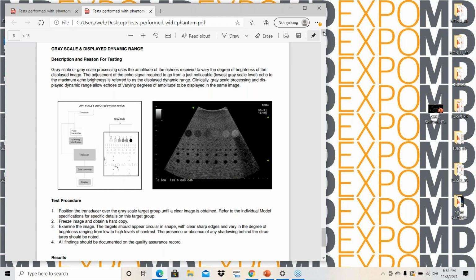I normally make it a mid one, so I have no problem reaching it. If I'm at 18 megahertz, I'm going to have a hard time getting here. So I try to get something around the 10 megahertz, depending on what the customer has. So I'm clearly getting beyond, and then it doesn't matter if you can see them all. It's the system's ability to differentiate, not the frequency. And so I only need to do this test on 1, and I will definitely have a printout, because an image quality problem, a lot of times, is based on this. The system loses its ability to see a specific density. Okay, make sense?